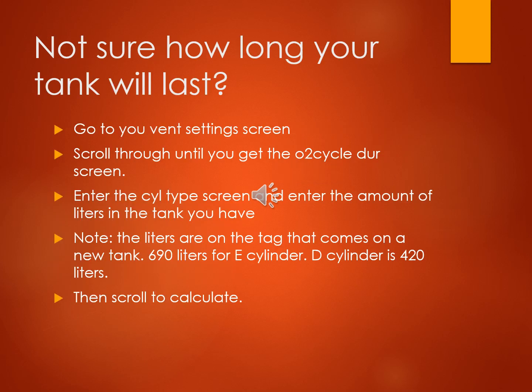All right, here's a really cool thing that these ventilators have on here. If you go to your vent screen and scroll through, holding that select button down, until you hit the O2 cylinder duration screen, you can enter the cylinder type and then enter the amount of liters in the tank that you have or the PSI that's left. The tanks will normally have on the side, you have 690 liters in the E cylinder. The D cylinder is going to be 420. And then you scroll over to calculate, and it'll give you an estimated time that you should have on that tank.